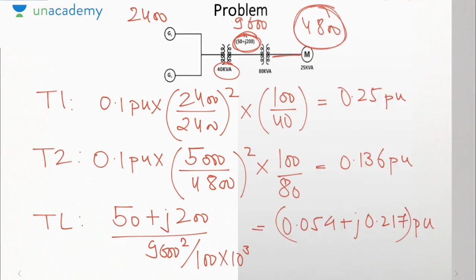For the motor, the impedance given is 0.2 pu and the voltage is 4 kV. But the voltage here on the motor side is 4800. So 0.2 into old voltage 4000, assumed is 4800. What about the MVA base or kVA base?